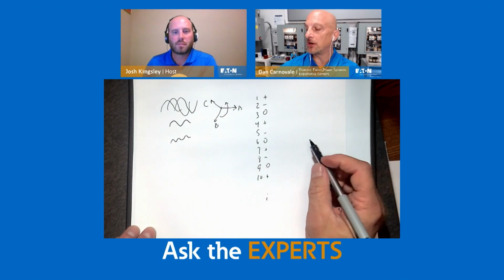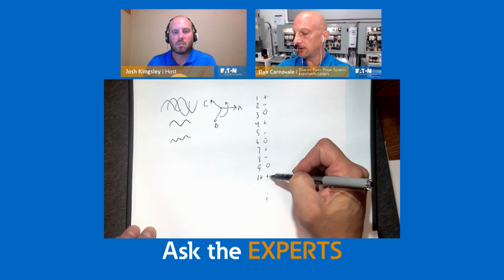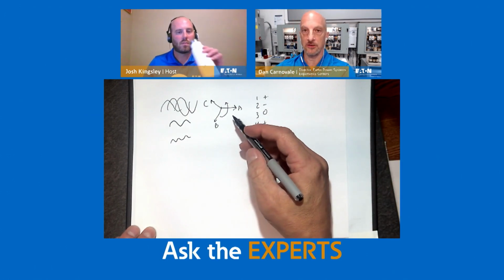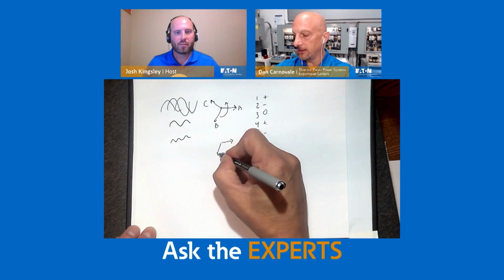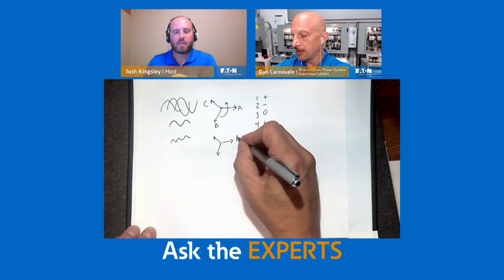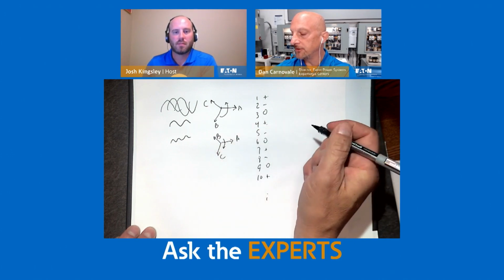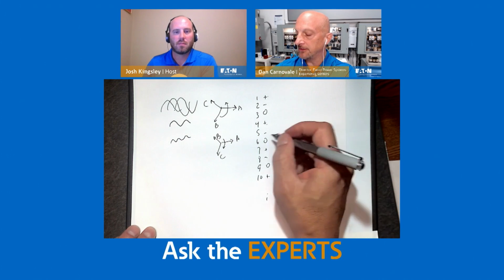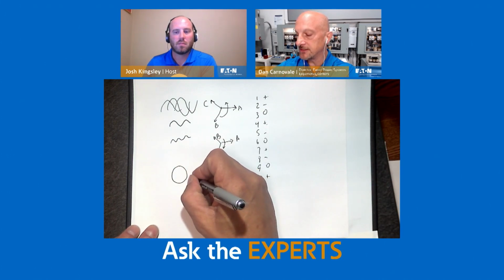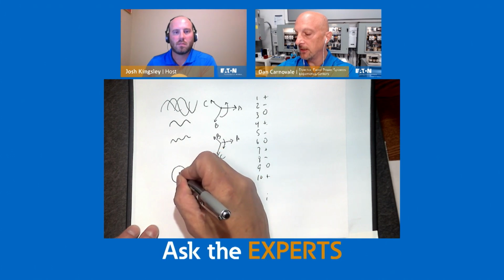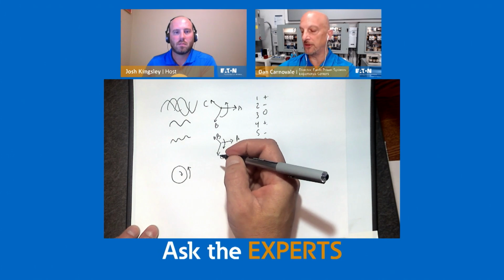Okay, positive sequence harmonics act like the 60 Hertz stuff. Negative sequence harmonics are kind of like A, B, C reversed. We talk about, let's say for a motor, we have a motor that spins and the 60 Hertz is making it spin this way. The negative sequence harmonics kind of make the motor want to spin the opposite way.